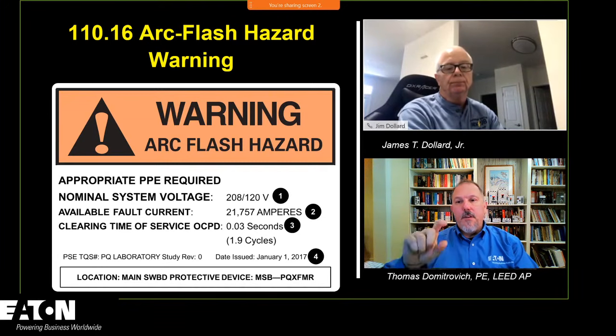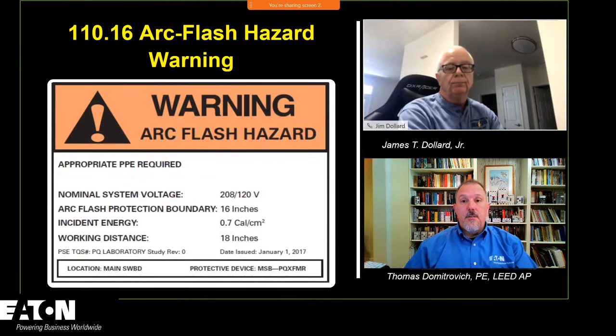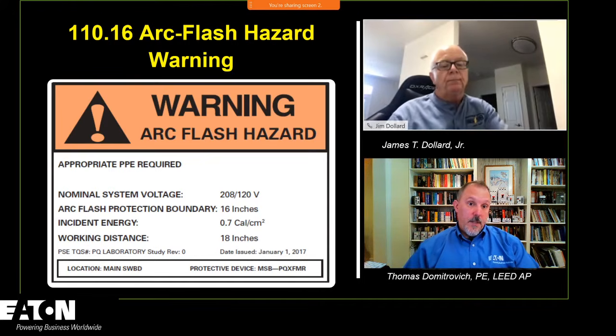This label follows suit with the table methods we have in 70E. You could use either of those methods covered in 70E, or the standard incident energy labels we always do from a calculation perspective. So there are various ways to address labeling. But this is the first foot in the door—if you wanted to expand these requirements to other locations, this is probably a good place to start.